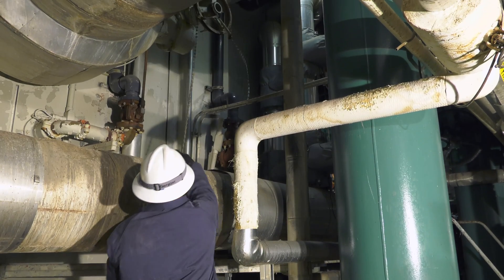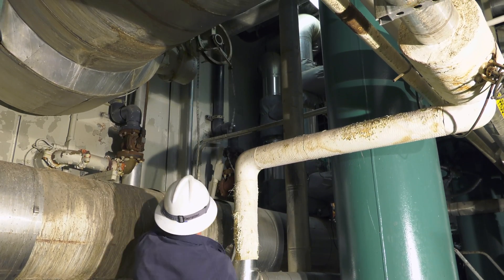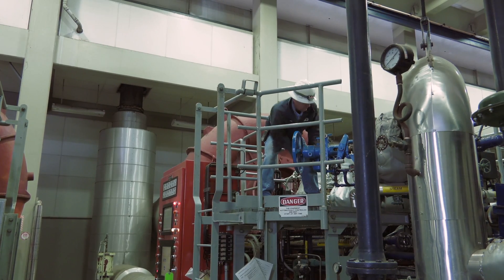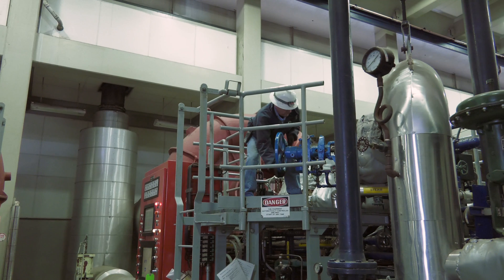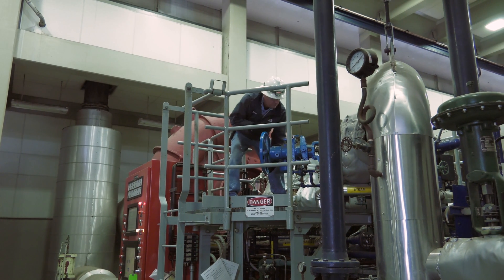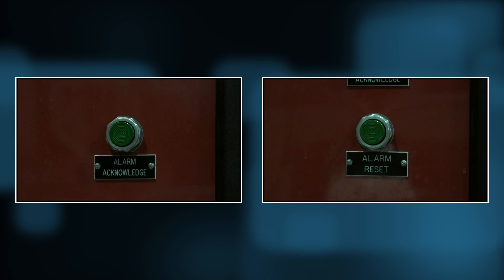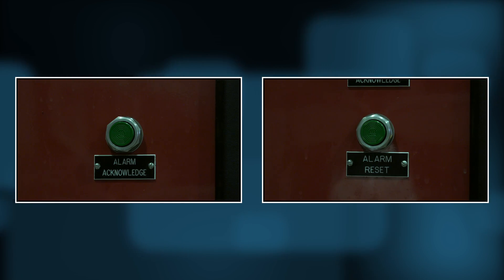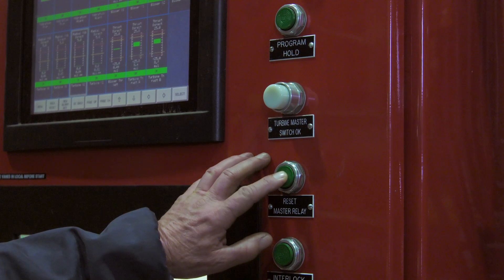Next, open the main aeration air header, then go back to the pump and blower building ground floor and verify the trip and throttle valve and the master relay are reset. If not, close the trip and throttle valve by spinning the wheel clockwise. Press the alarm acknowledge and alarm reset button, then press the master relay reset button.